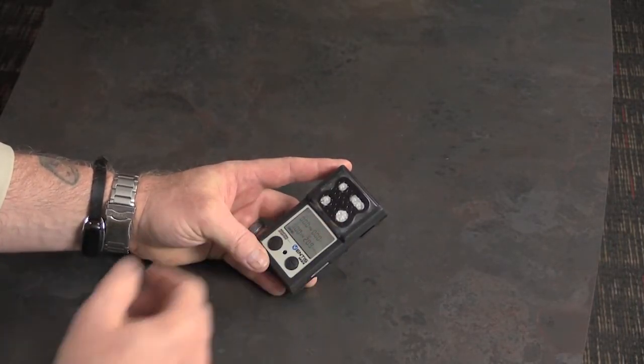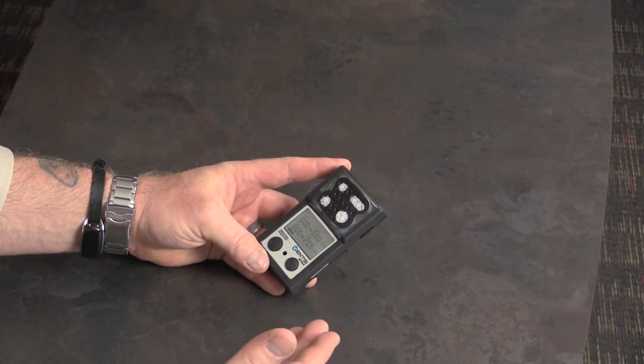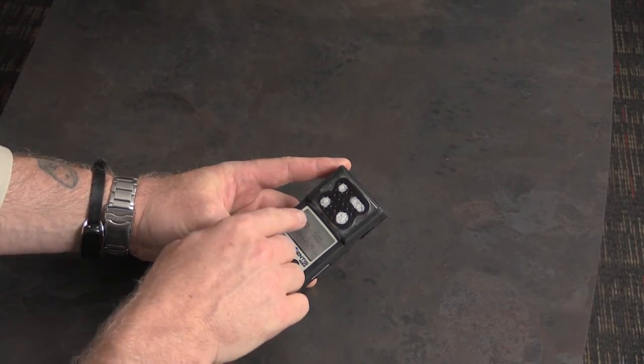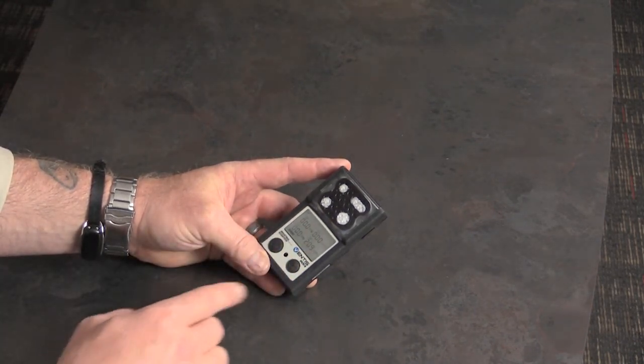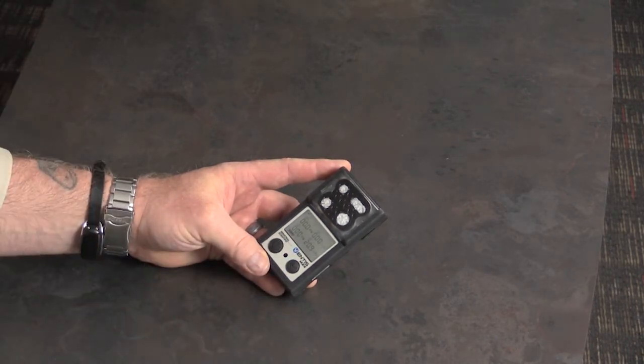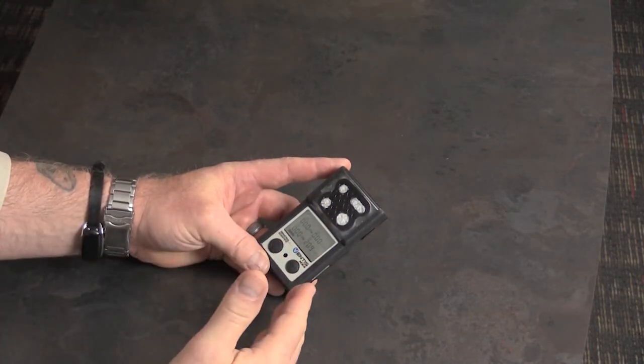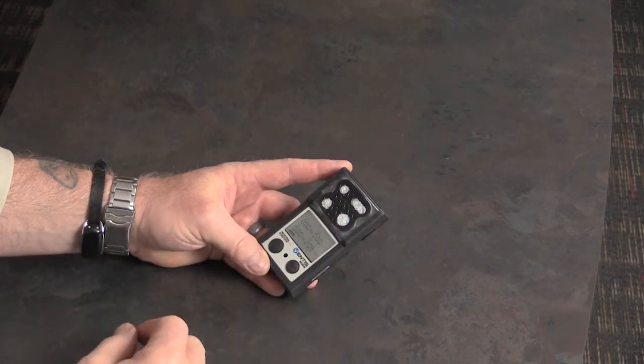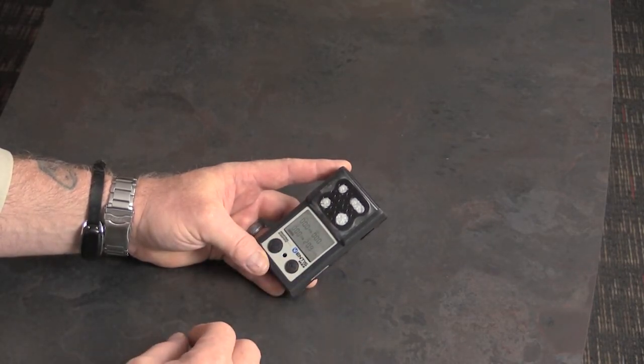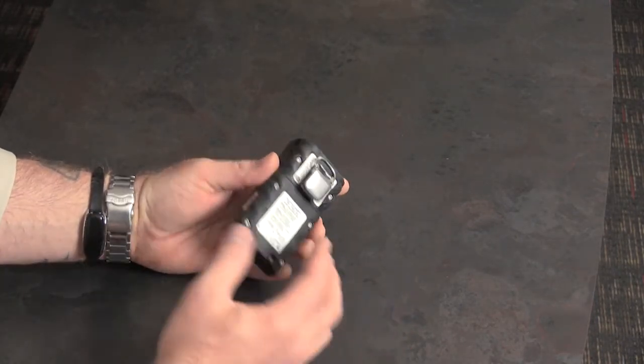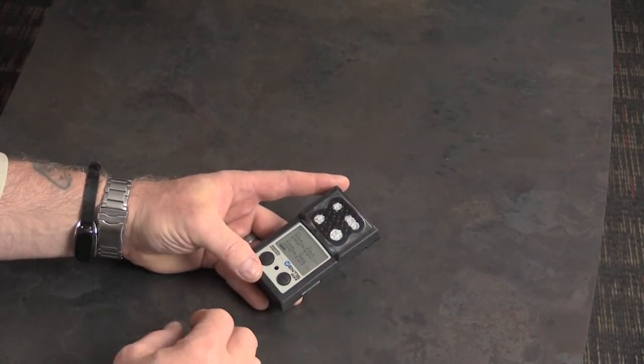Now we're back at the home screen. The instrument's stable, looks great. I've got zeros for my toxic and my LEL sensors. My oxygen's reading 20.9. At this point I can conduct my calibration and my bump test and start using the instrument for work. I gotta say, it looks brand new - it looks exactly like a new unit would.